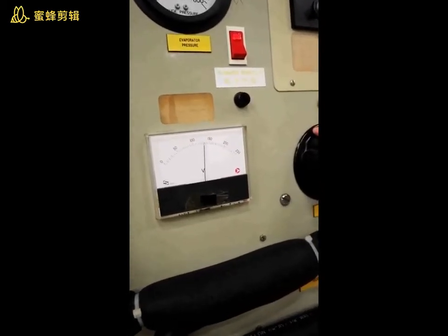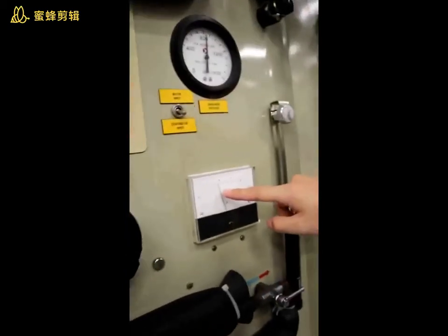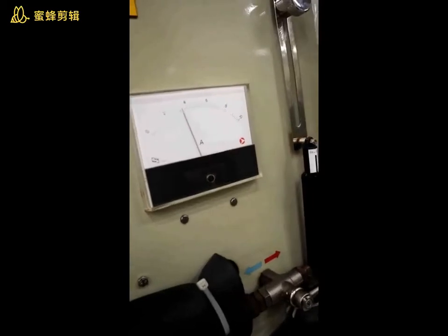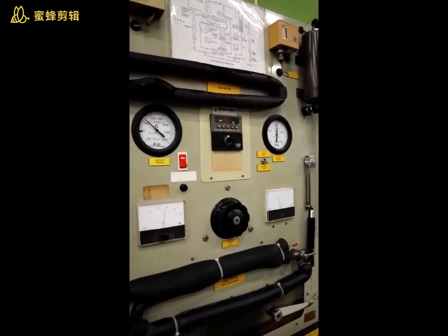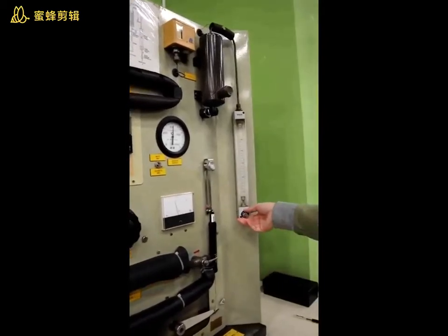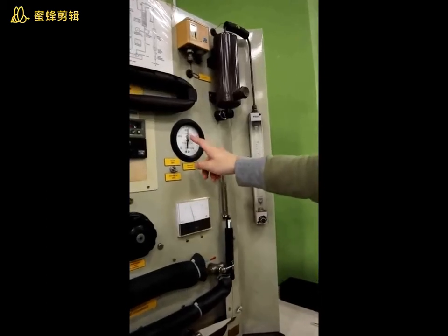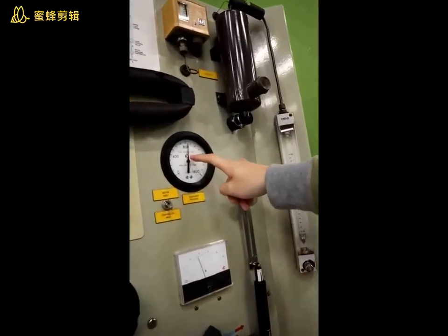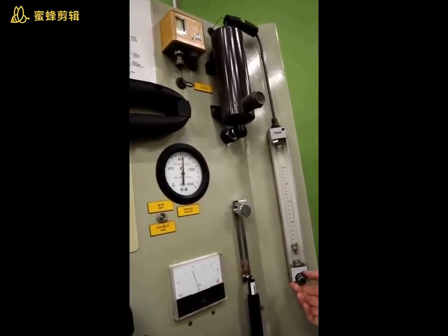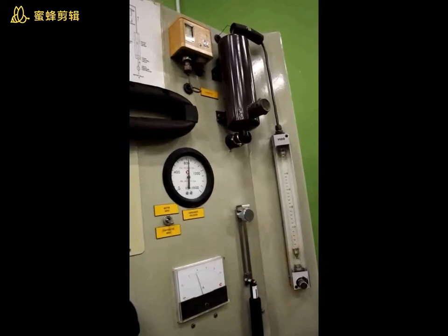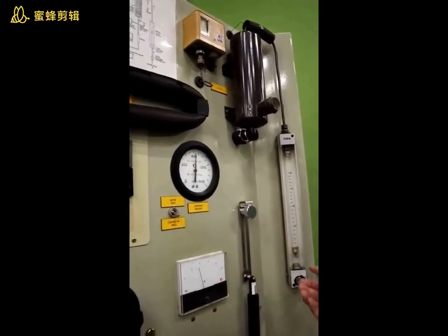The voltage is close to 150, while the current is more than 3, so the total heat input rate is 400 watts. We wait a moment, but before that, we have to make sure that the condenser pressure is still maintained at 800. After it reaches 800 and works at a stable condition, we then record those 7 temperatures.